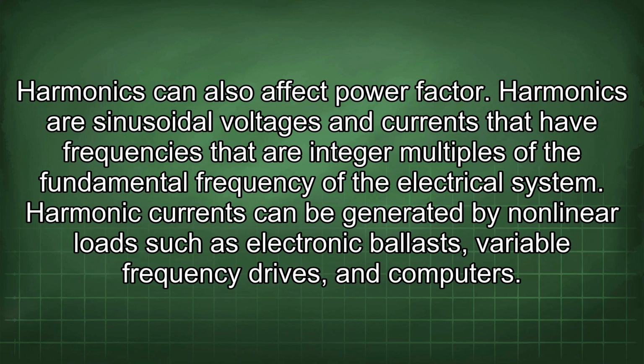Harmonics can also affect power factor. Harmonics are sinusoidal voltages and currents that have frequencies that are integer multiples of the fundamental frequency of the electrical system. Harmonic currents can be generated by nonlinear loads such as electronic ballasts, variable frequency drives, and computers.